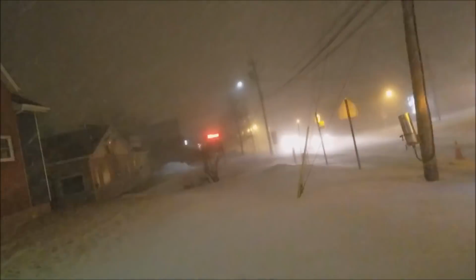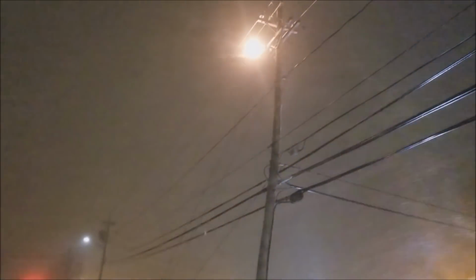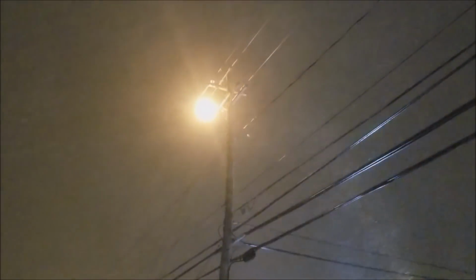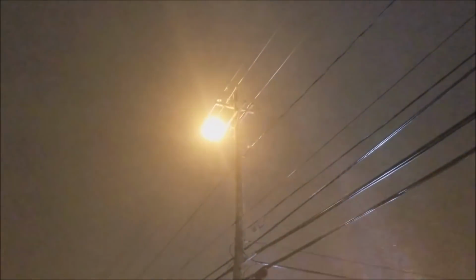This ball of fire you see now is essentially a visual interpretation of how much power it takes to turn on 24,000 light bulbs. 2 minutes before this video was taken, I was approximately 12 feet away from that ball of fire as I was returning service to the lines. The cause of the fault was actually a faulty switch, in which the fuse did not make proper contact. As soon as the arc started, I quickly lowered myself to the ground, got into a safe position, and phoned the dispatcher to advise him that the substation was probably going to trip. I also made sure to keep the area clear of any curious onlookers, until eventually, the arc just burned itself out. Luckily, it didn't cross phase.